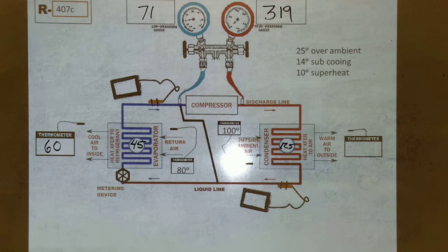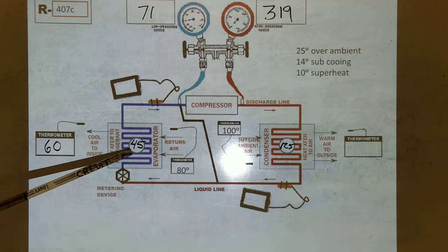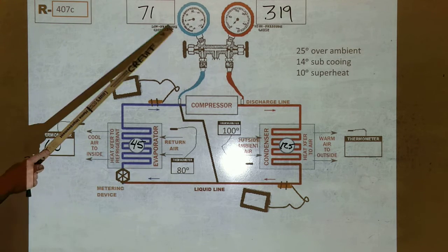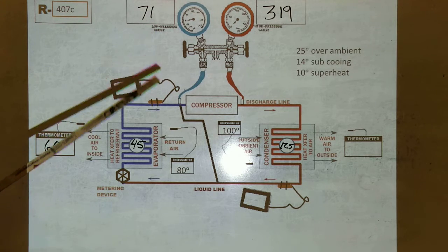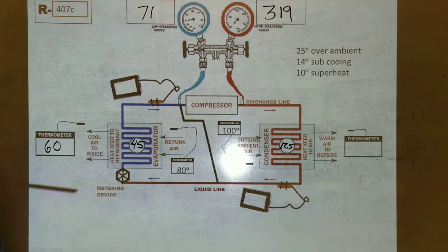On the chart, and especially on the 400 series refrigerants, we're talking about 2 or 3 different refrigerants in that 407C. What's happening is it's fractionating, changing pressure and temperature at different rates. So if it's 45 degrees here, then it's not really 71 here, because the components inside are boiling off at different temperatures. That's fractionization, so we have what they call a temperature glide.